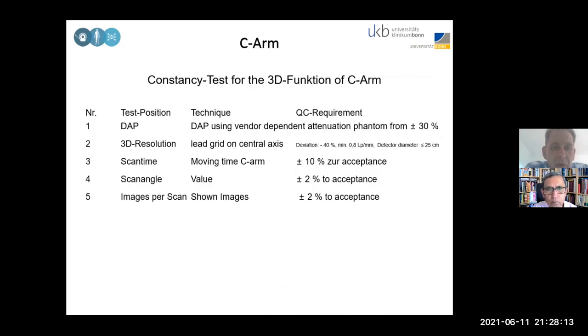Here we are. So then we have to go the lead grid and the central axis. So you see that the acceptance in radiography really accepts 40% deviation in position of a grid, and 0.8 line pairs per millimeter is the minimum you should actually accept. If you would accept 0.8 line pairs per millimeter in mammography, you would fail with all diagnosis in mammography. There you actually need something like 3 or 4 line pairs per millimeter. So you definitely have to have a higher resolution there.